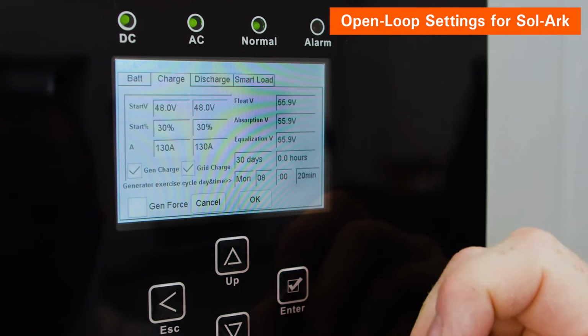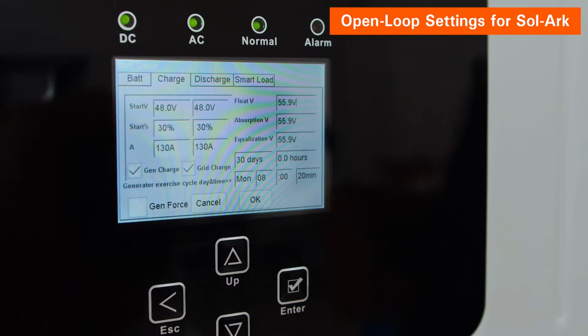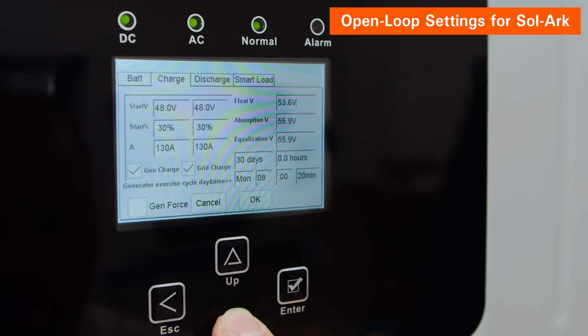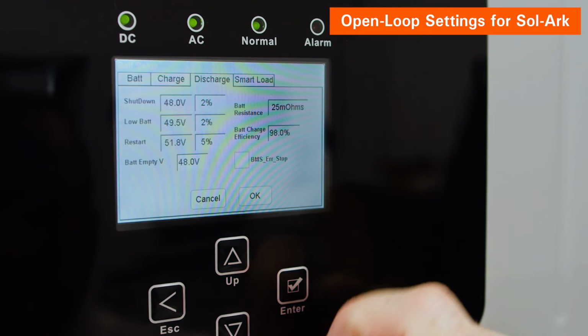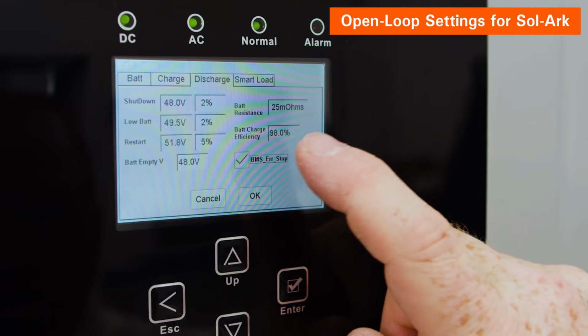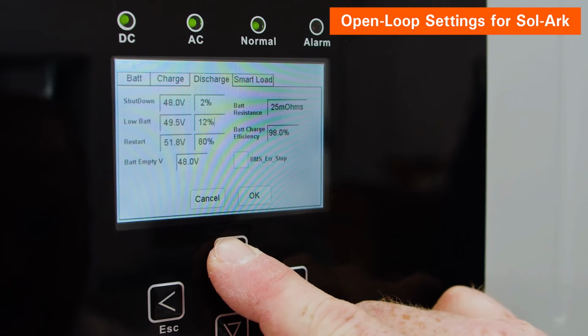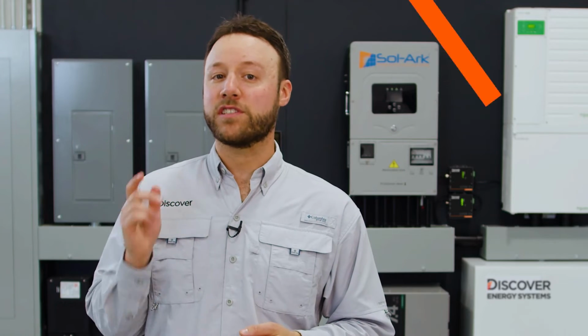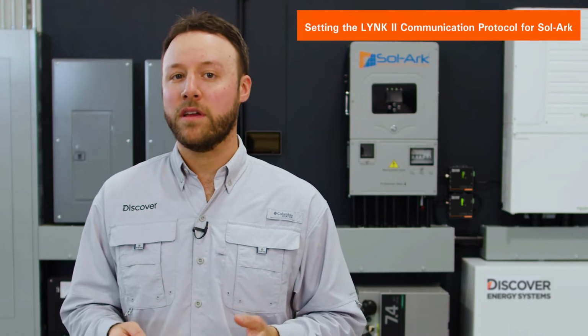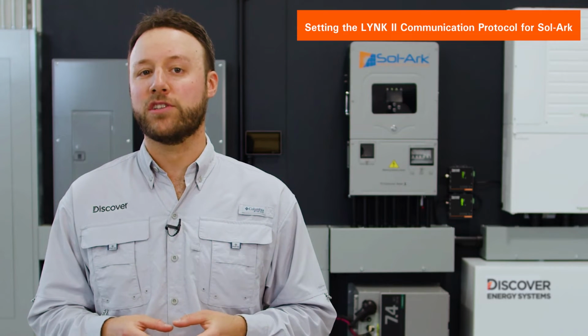Next, set the absorption voltage, float voltage, and other voltage-based parameters on the charge screen. On the discharge screen, disable the BMS error stop function and set the other voltage-based triggers. After establishing open-loop configuration, we can configure the LYNK II Gateway to use the Sol-Ark communication protocol.